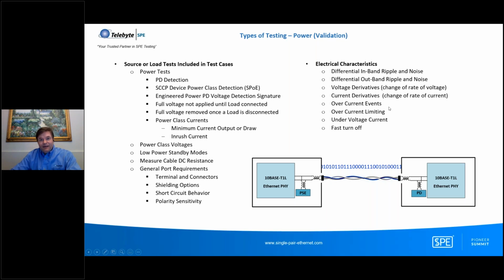We also look at measuring some of the electrical characteristics on the data pair for ripple noise, slew rates of voltage and current, and fault conditions. So this is a picture. You have your 10BASE-T1L PHY, and then you usually have your power coupling. You have a voltage source here, voltage supply and current, and we're sending current and voltage over the same twisted pair and then receiving that power over the pair and powering up this device, all with the same two-wire cable that has data and power on it.